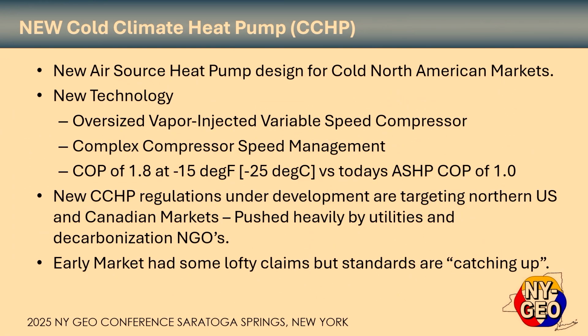So now there's a new air source heat pump design for cold climates, and it's called the cold climate heat pump. It's been around for a few years, but the technology is a little bit new, and it's a little bit morphing at this particular point in time. It's basically an oversized vapor injected variable speed heat pump, and that vapor injection gives you some benefits when you're doing heavy lift, meaning really cold outdoor temperatures, trying to pull heat out of the air and then put it into the airstream inside the home.